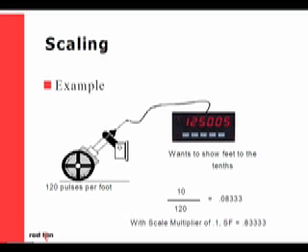Our example shows this application requiring feet to the tenths to be displayed. We see that our sensor gives off 120 pulses per foot. So our equation becomes 10 over 120, or 0.08333. When we add a scale multiplier of 0.1 in the programming, our scale factor then becomes 0.83333.